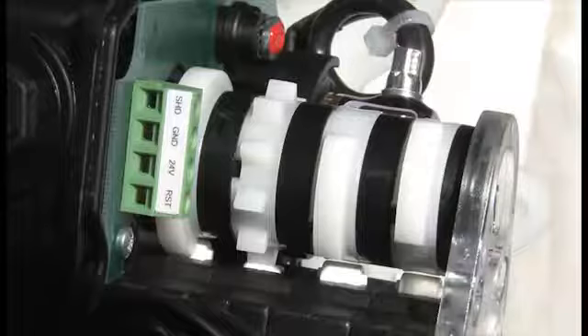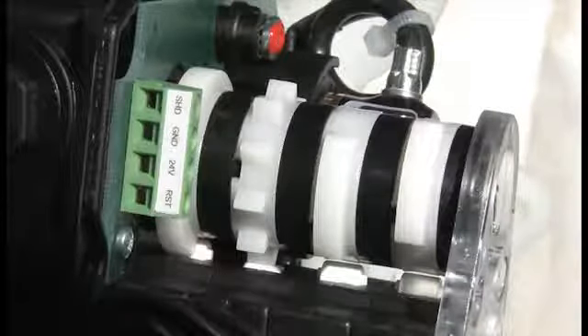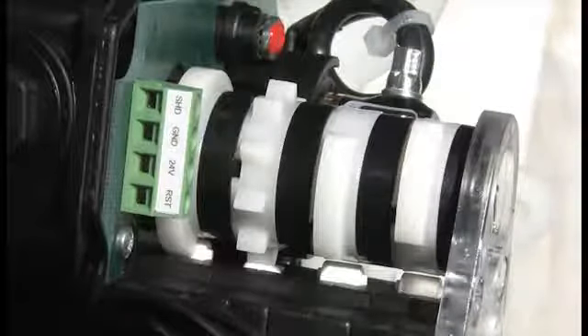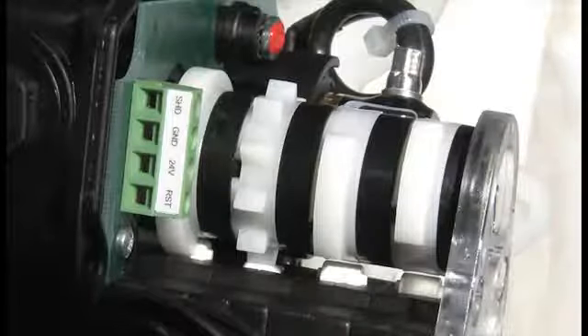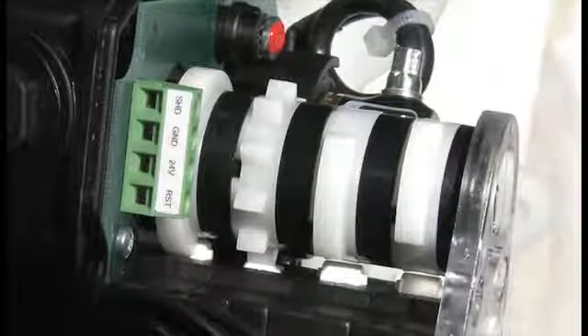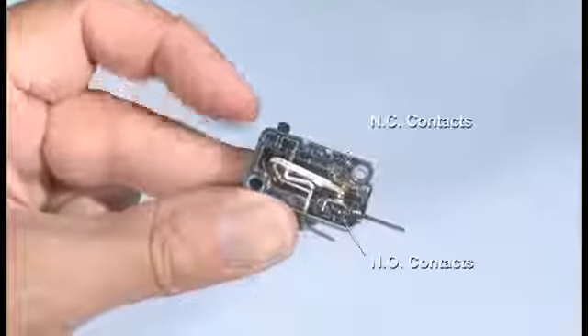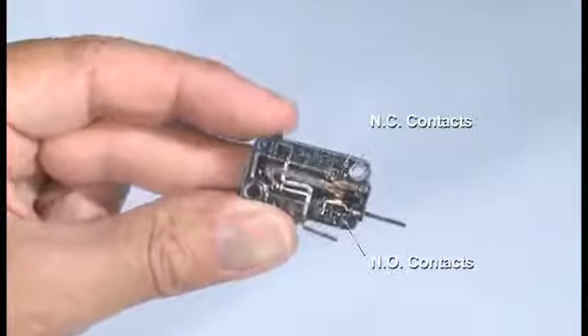Gear ratios of 150 to 1 are typical of yaw position limit switch mechanisms. Limit switches may be connected to any voltage, AC or DC. They do not consume any power, and they are easy to install and adjust. Most limit switches have both normally open and normally closed contacts available.